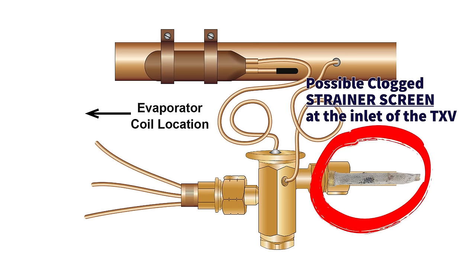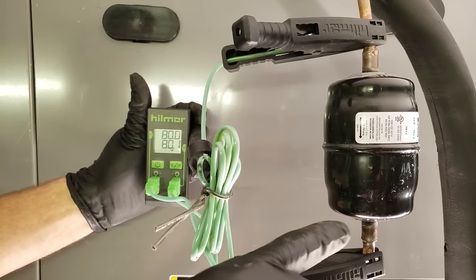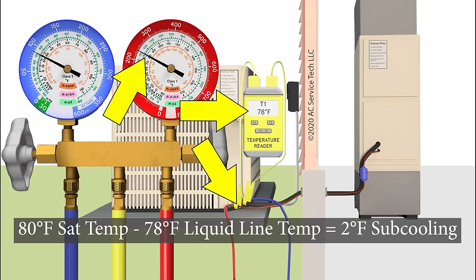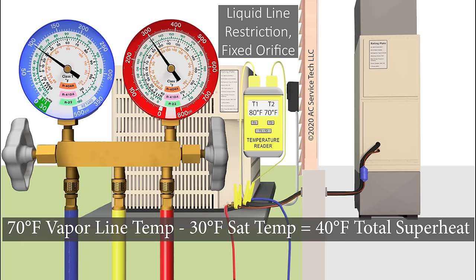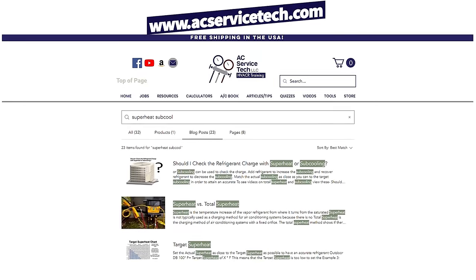You could have a clogged strainer screen at the inlet of the TXV, or a liquid line restriction at your filter dryer — which could be broken inside, or the pre-filter could be clogging the refrigerant from traveling through, causing a pressure drop before it even reaches the thermostatic expansion valve. You can refer to quick reference cards to determine the difference: a low refrigerant charge shows high superheat and low subcooling, while a liquid line restriction shows high superheat and normal to high subcooling.